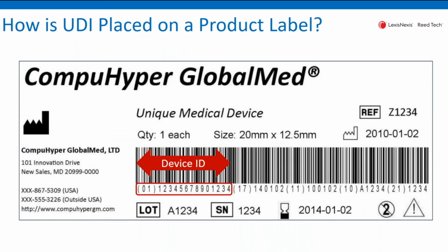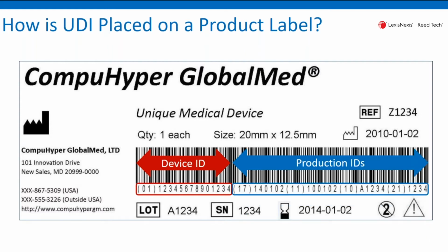When you place that UDI on the label, you'll find that in some cases it takes a lot of real estate. Now this is exaggerated a little bit for the particular sample that we have here, but the device identifier, and in this particular example, we do have 4 of those production identifiers on the label. So the manufacturing date, expiration date, lot, and serial number are all on the label itself. So because of their presence, they need to be included with the UDI.